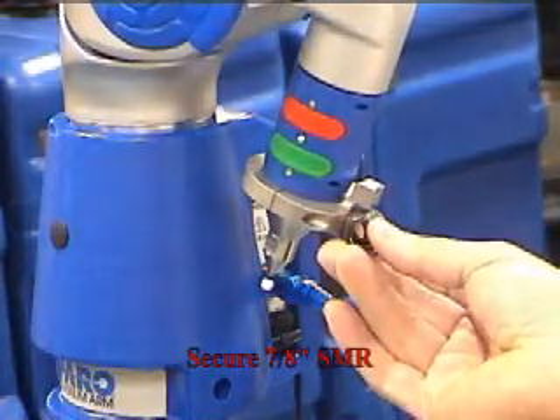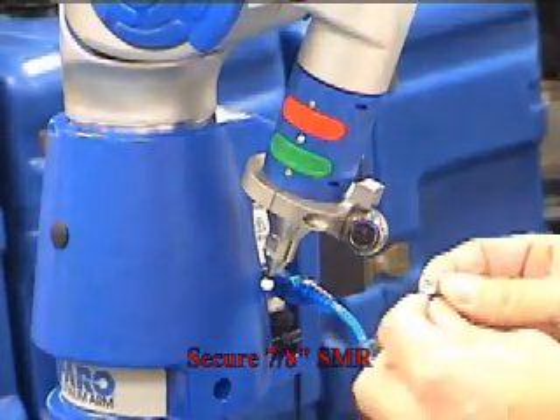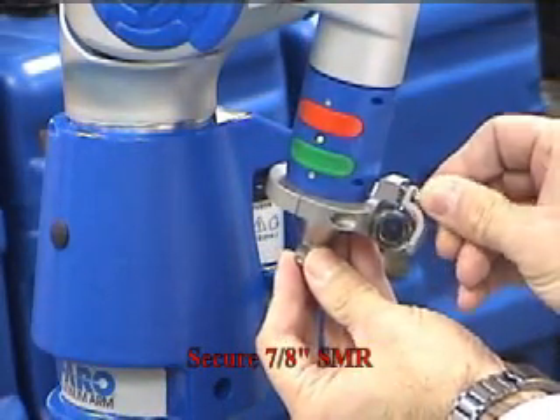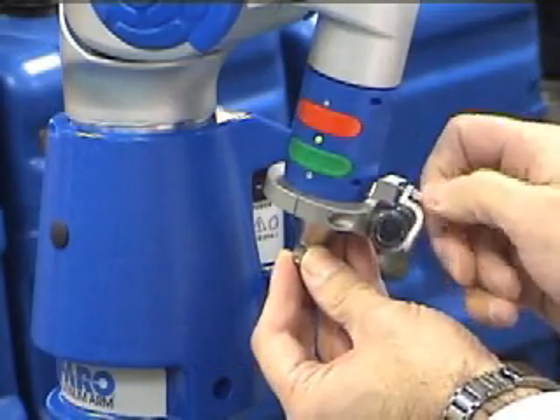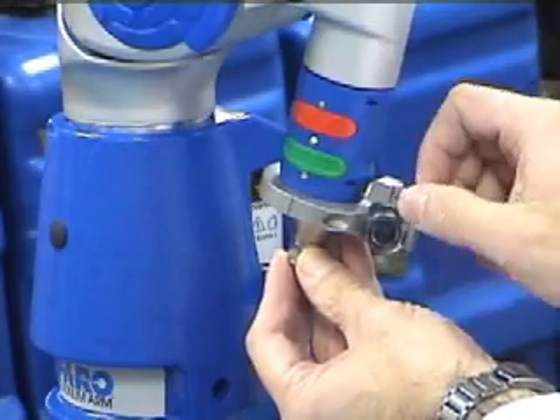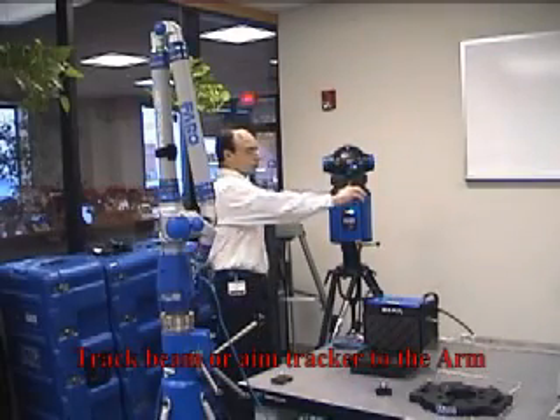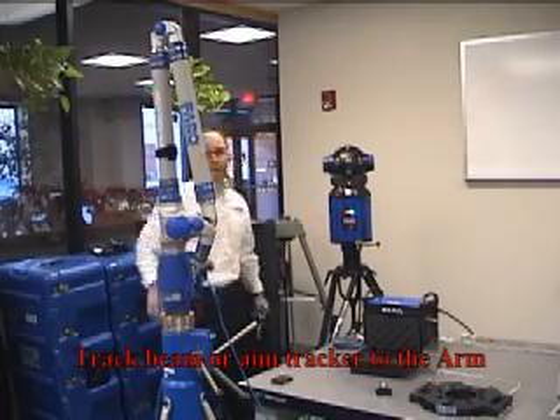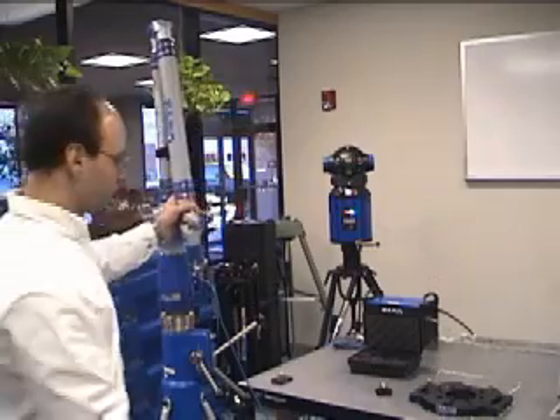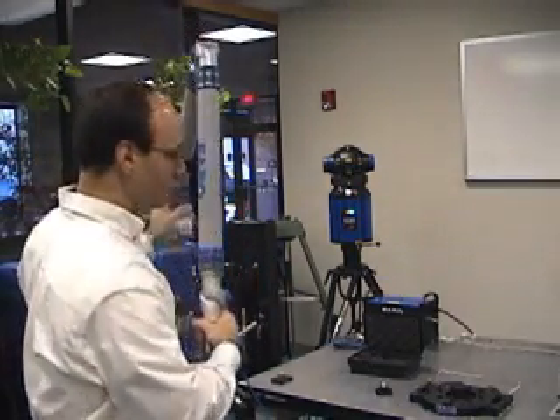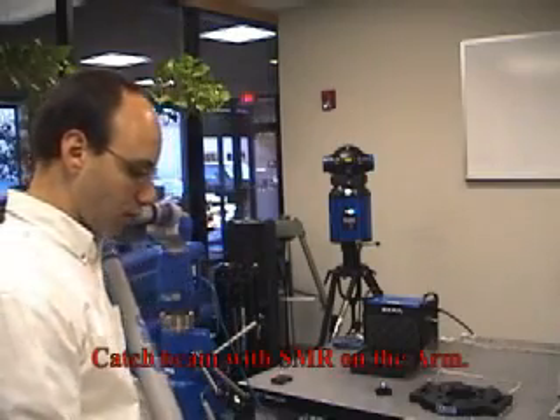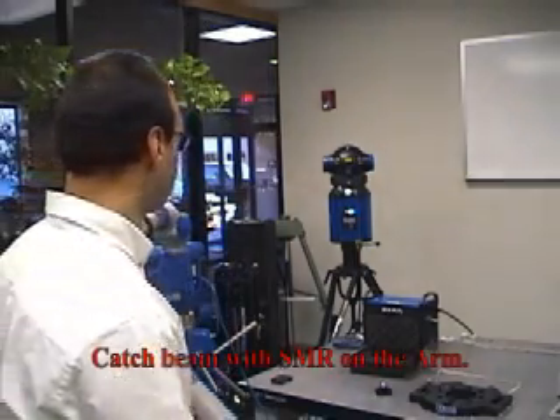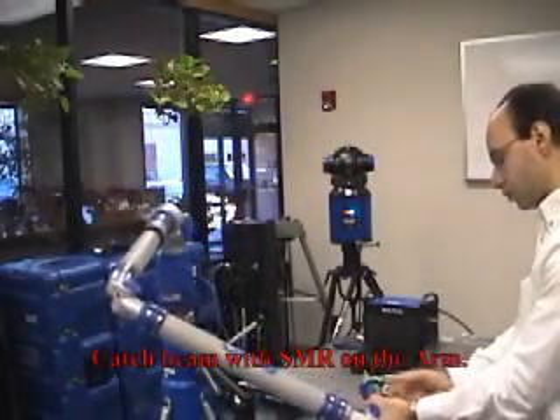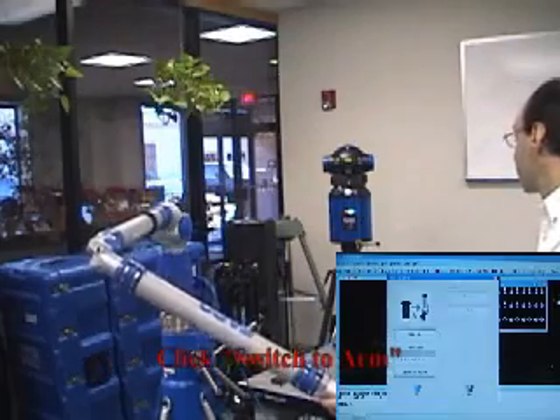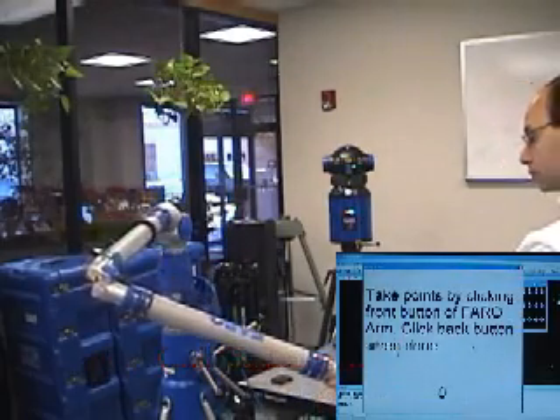Measuring with the TrackArm. To measure with the TrackArm, first secure the 7/8 SMR onto the arm. Now you're ready to begin measuring with the arm in the tracker's coordinate system. First, track the beam out toward the arm, and then take the arm and catch the beam with the SMR at the end of the arm. Then click on the Switch to Arm, which will bring up the dialog to begin collecting data.